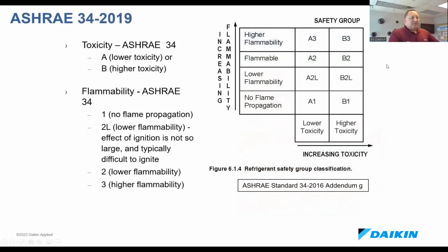In ASHRAE 34, there's a refrigerant safety group classification where you've got increasing toxicity on the bottom—an A is lower toxicity, a B is higher toxicity. ASHRAE never says non-toxic, just lower and higher, because in the right instances, water can kill you—you can drown in it. On flammability, you've got a 1 as no flame propagation up to a higher flammability of 3.